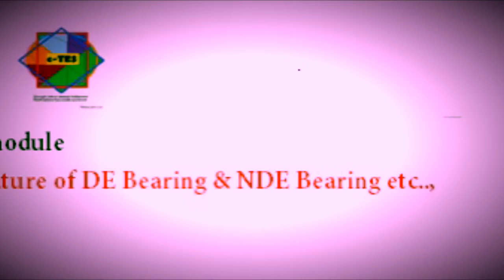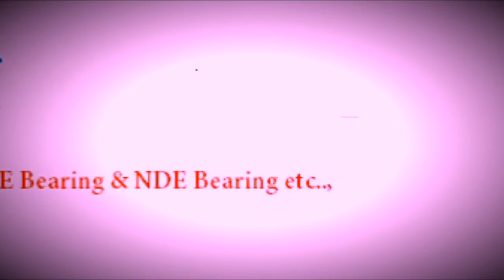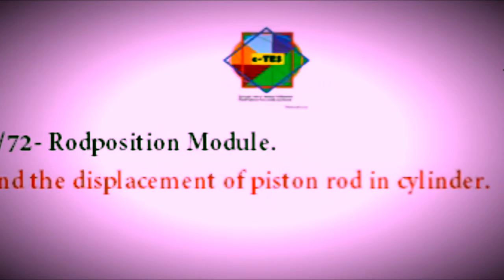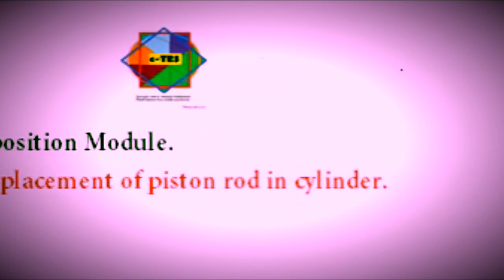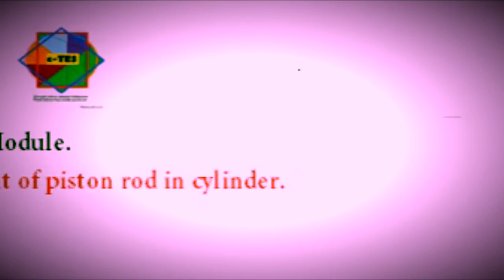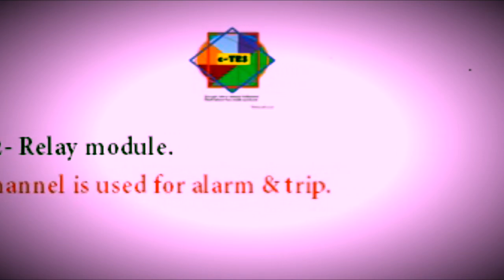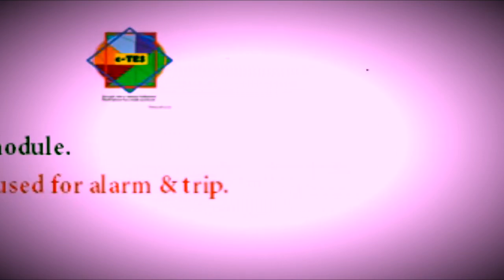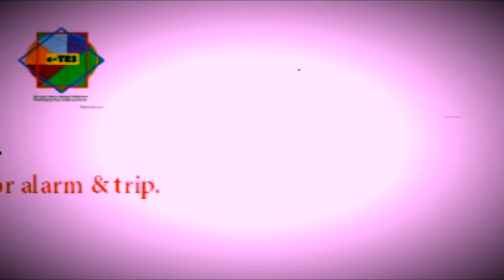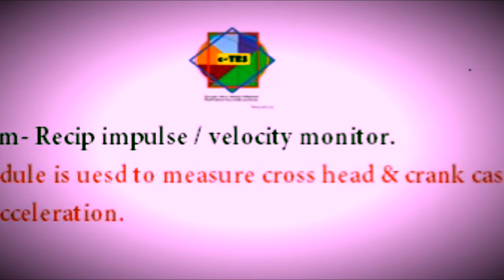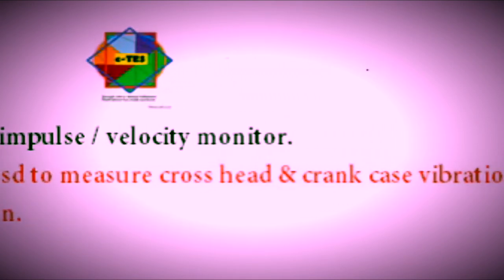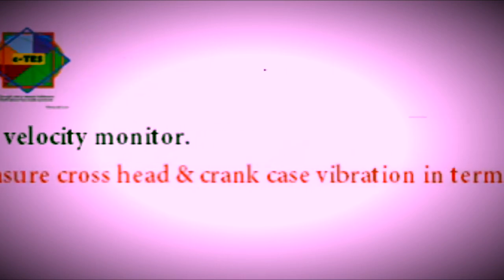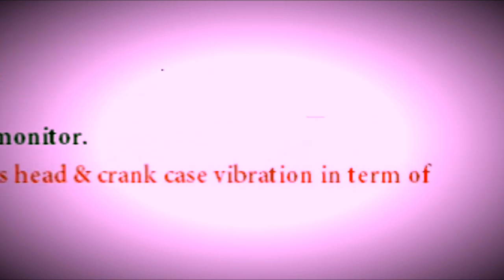The 3500/75 is used for radial vibration monitoring. The 3500/72 is a rod position module, simply called a rod drop monitor. The 3500/32 is a relay module used to make alarm as well as a trip in a danger situation. The 3500/70 is a velocity module used for crosshead and crankcase vibration in terms of acceleration.